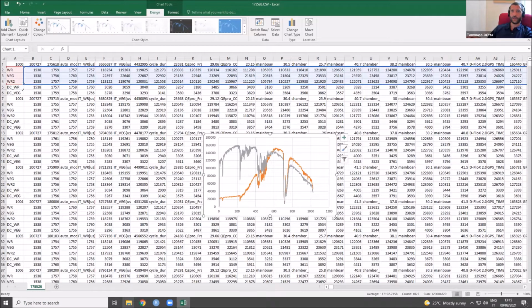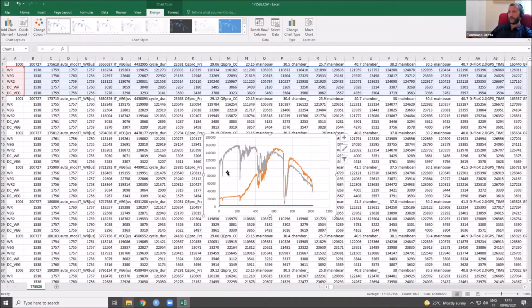And finally, we are always collecting for every cycle also the dark current, which means the internal noise of the instrument, which can affect the radiance and the accuracy of the estimate of the reflectance, radiance, fluorescence, and vegetation indices.